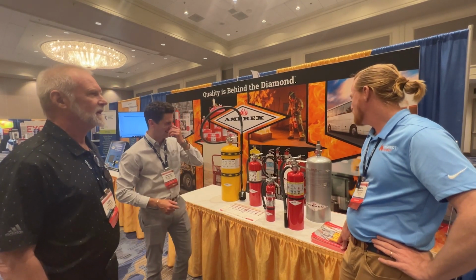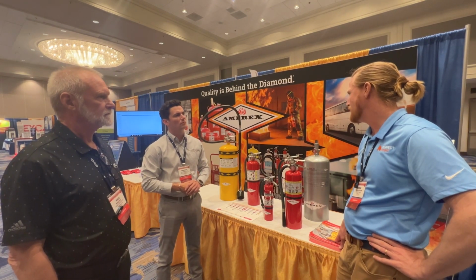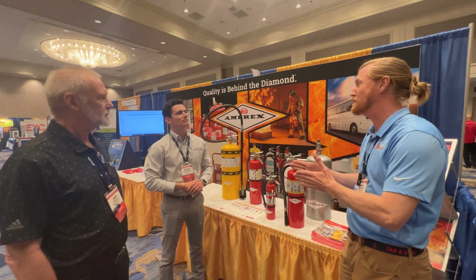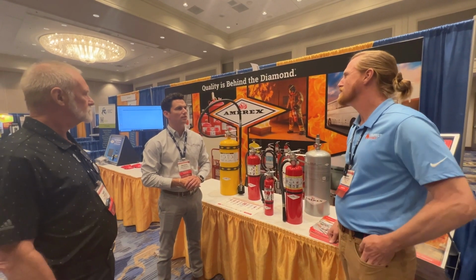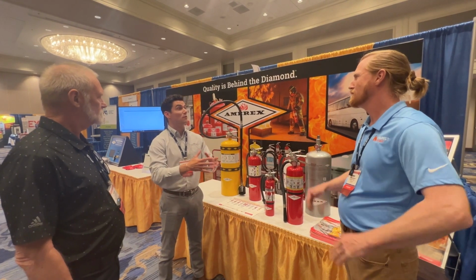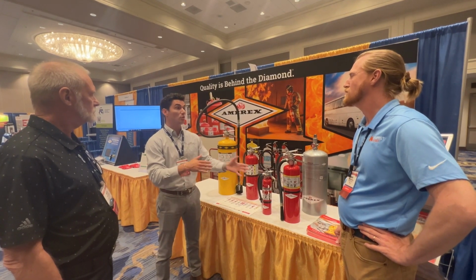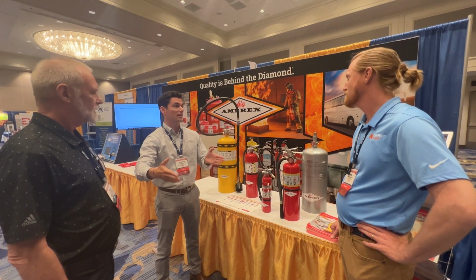Thank you very much. Now, does the 12 year kind of align with the NFPA 10 teardown time frame? It aligns right with that 12 year, right? That's exactly right. Yeah. At that point, you're at the hydrostatic testing and that breakdown. That's what we're really looking for. So basically, we're saying that we're verified for the corrosion because no other unit is covered for corrosion. Only this unit. Right. So up until the first breakdown, we will cover that. Yeah. And it's UL verified.